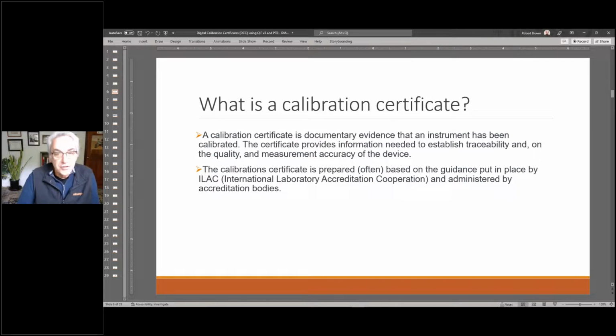Now, what is a calibration certificate? It is documentary evidence that an instrument has been calibrated. The certificate provides information needed to establish traceability on the quality and the measurement accuracy of the device. Calibration certificates are often prepared based on the guidance that are put into place by an international laboratory accreditation cooperation and administered by accreditation bodies such as the A2LA.